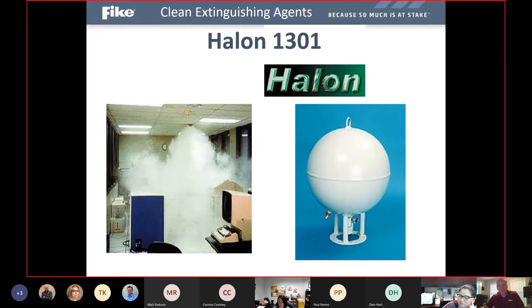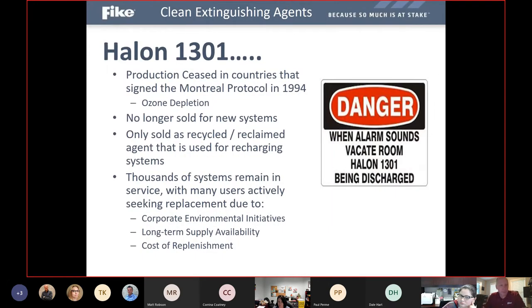The original agent for clean extinguishing systems was Halon 1301. Halon 1301 was very popular for many years, but ultimately in 1994, it was determined and evaluated to be a severe contributor to ozone depletion. So it was basically banned from production back in the mid-90s to a point where it could no longer be sold for new systems, and it could only be used to recharge existing systems that might have discharged.